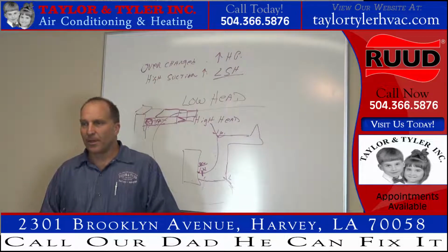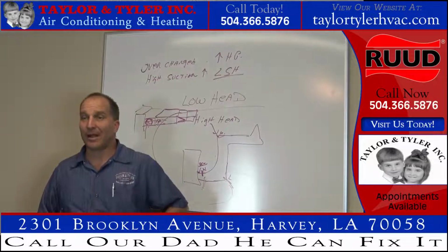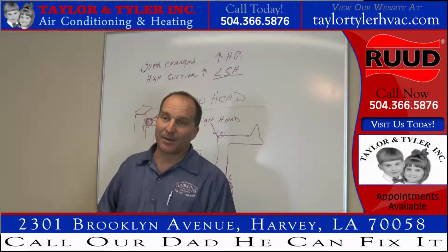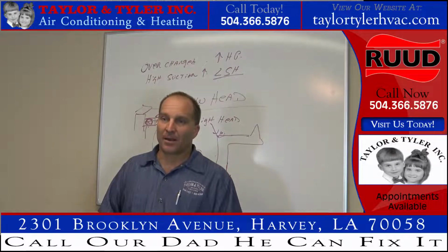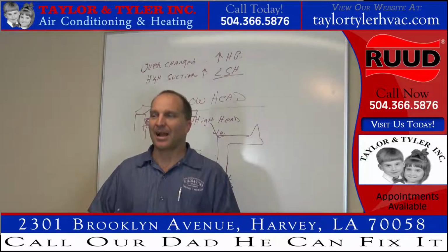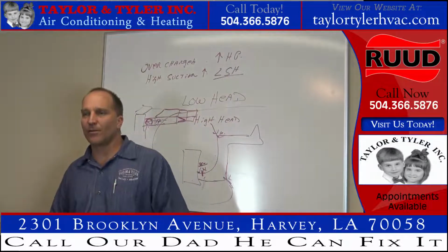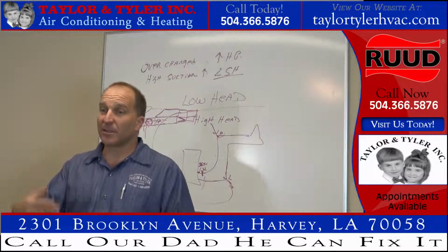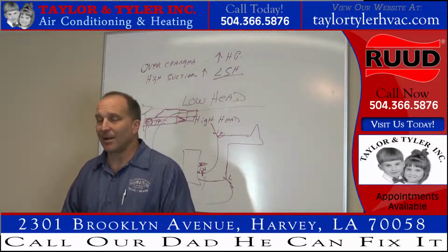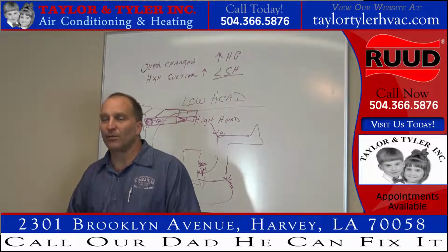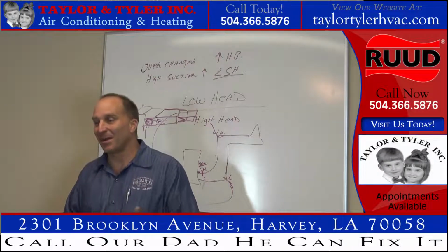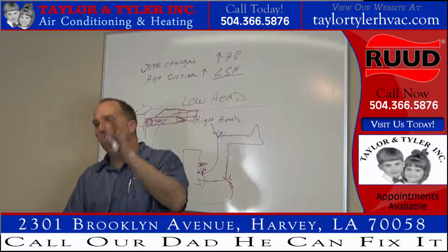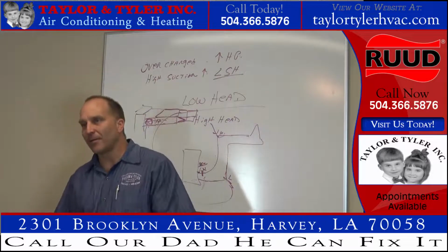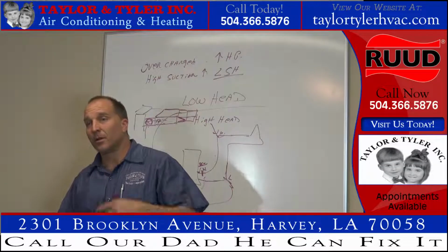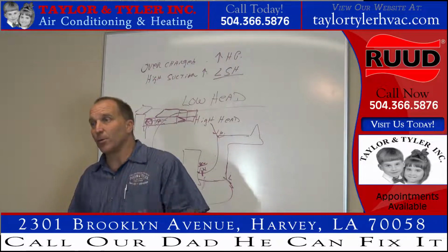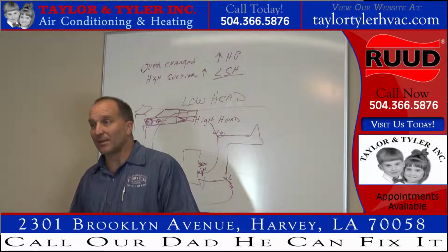Okay? So if I've got a real high heat load, like my gas furnace is working at the same time my air conditioning is working, then I'm going to have a real high suction pressure. I'm going to have a high superheat because there's too much heat running over that evaporator coil, right? And I don't care if it's a piston or a TXV. It's not going to maintain a constant superheat if I'm running 150 degree air over it. It's going to be a high superheat. The valve is going to be wide open. Your suction pressure is going to be jacked up high. And I don't care if your system is low on refrigerant or has too much refrigerant in it, it's going to have a high superheat. Okay? Because when you run your gas furnace, that's what's going to cause it.